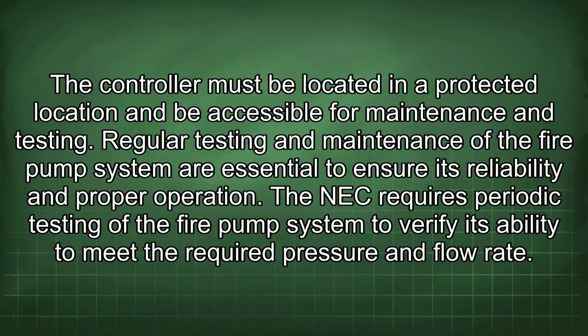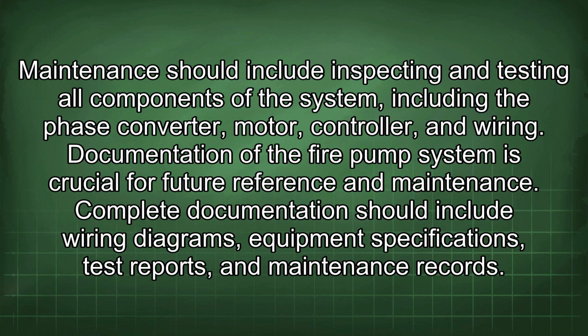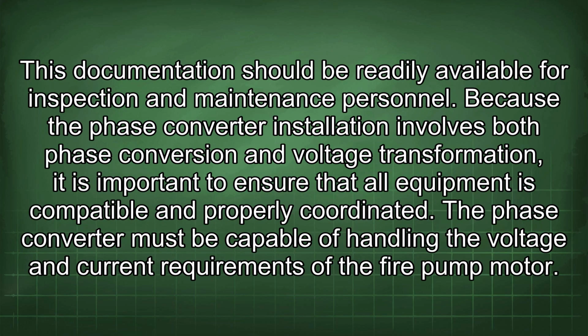Regular testing and maintenance of the fire pump system are essential to ensure its reliability and proper operation. The NEC requires periodic testing of the fire pump system to verify its ability to meet the required pressure and flow rate. Maintenance should include inspecting and testing all components of the system, including the phase converter, motor, controller, and wiring. Documentation of the fire pump system is crucial for future reference and maintenance. Complete documentation should include wiring diagrams, equipment specifications, test reports, and maintenance records. This documentation should be readily available for inspection and maintenance personnel.